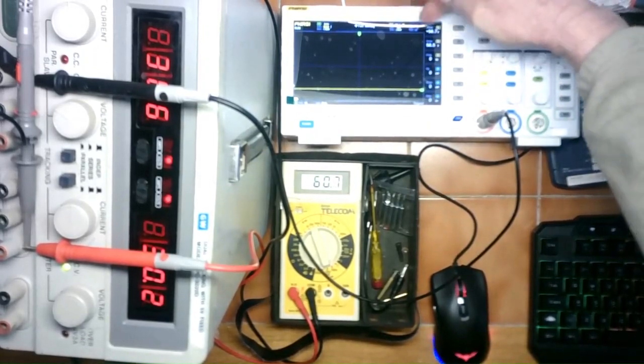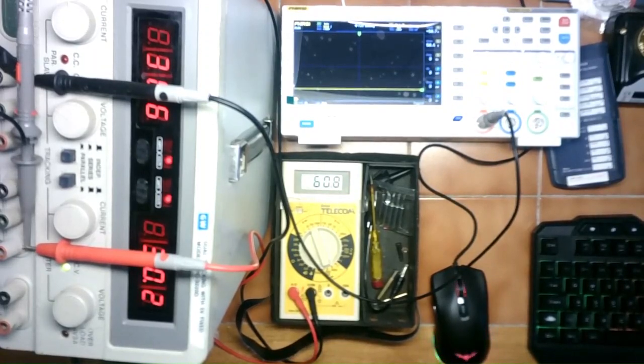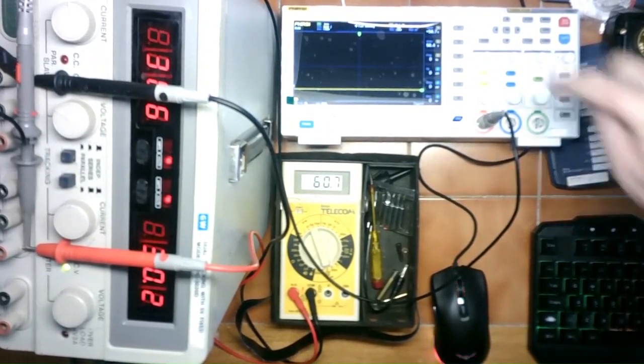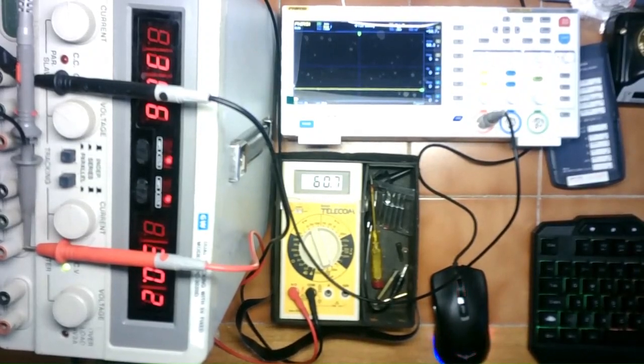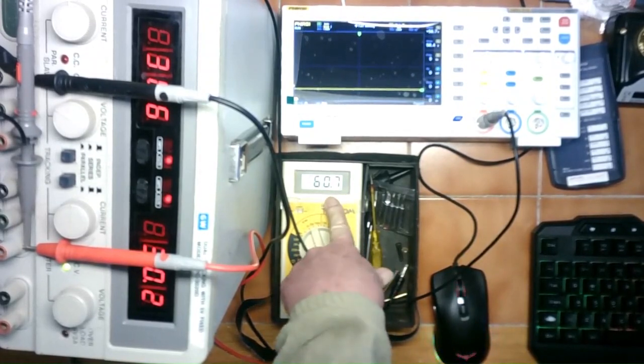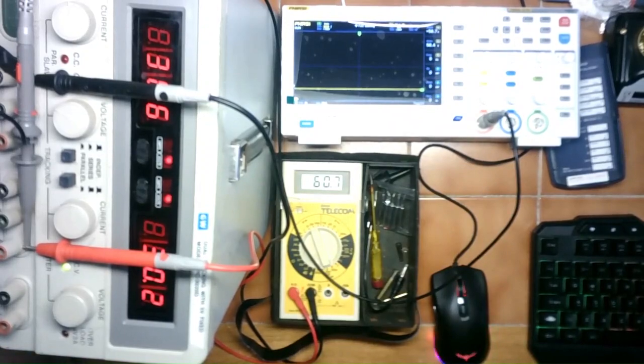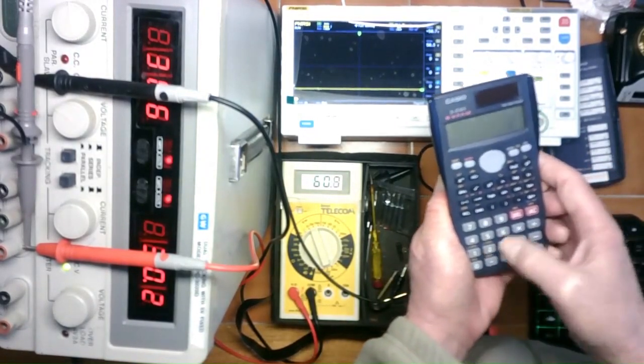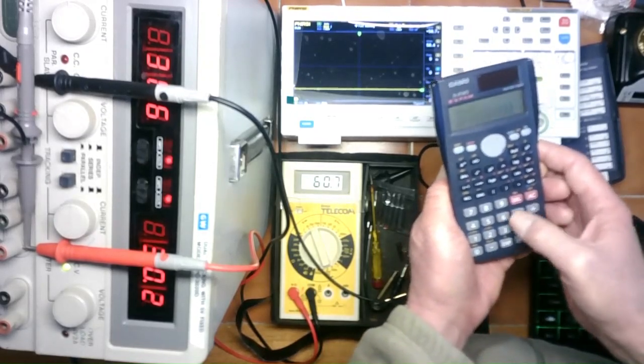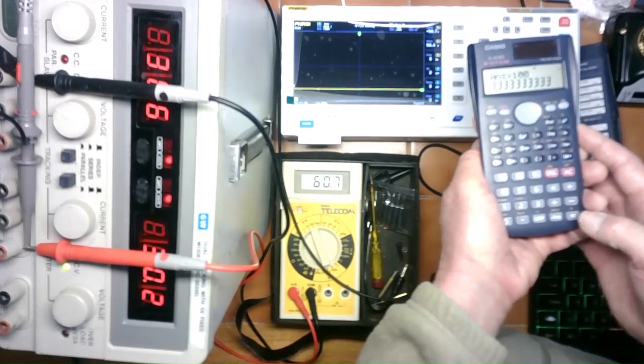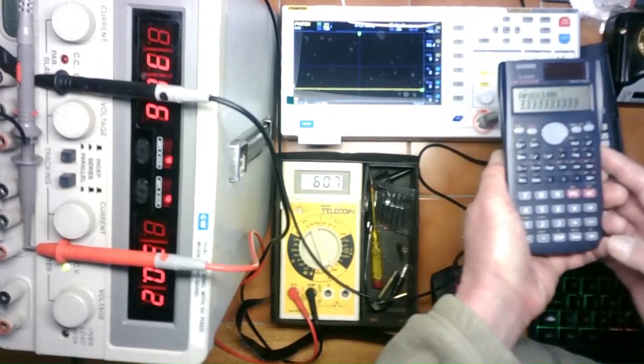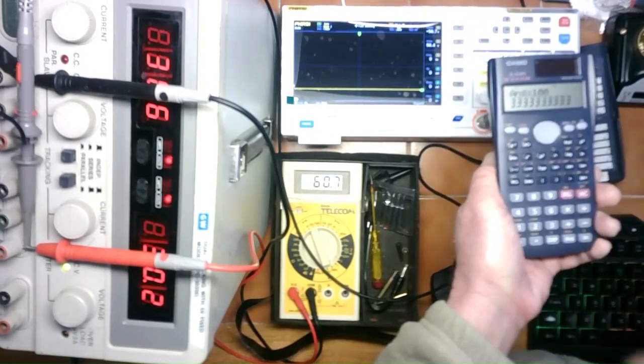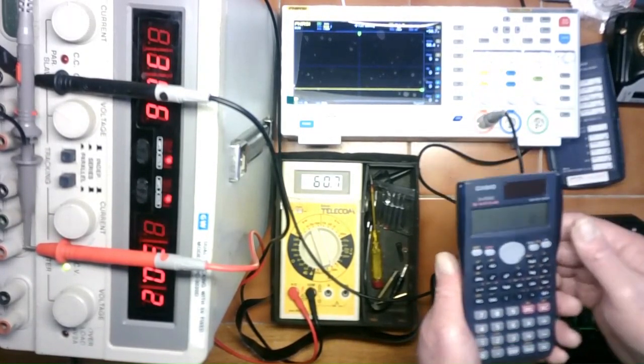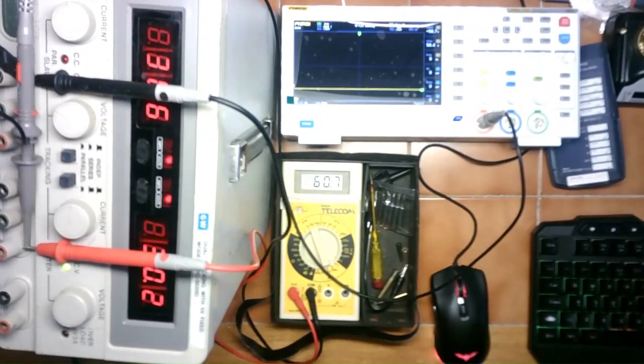Then on 100 you'd want to do that percentage calculation for its inaccuracy, to see the percentage difference between what it should be reading and what it's telling you on the Vmax scale here, which in this case is 58.7, when it should be reading 60.7. So again, it's 2 volts out on 60. If you did that calculation, you'd have 2 divided by 60 and then multiplied by 100, and now you've got 3.33% inaccuracy on a 60 volt DC input range. Okay, so I hope that helps you get perspective on what the limitations of the gear that you're working with are.